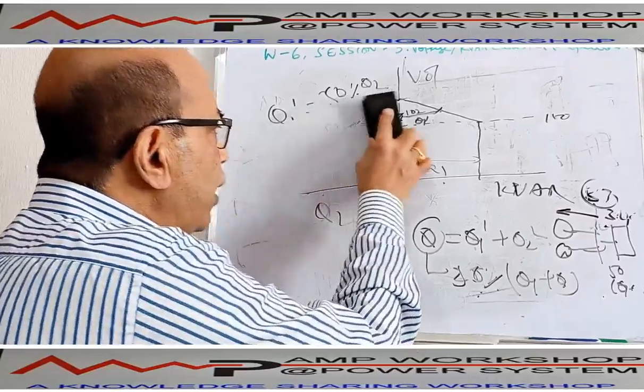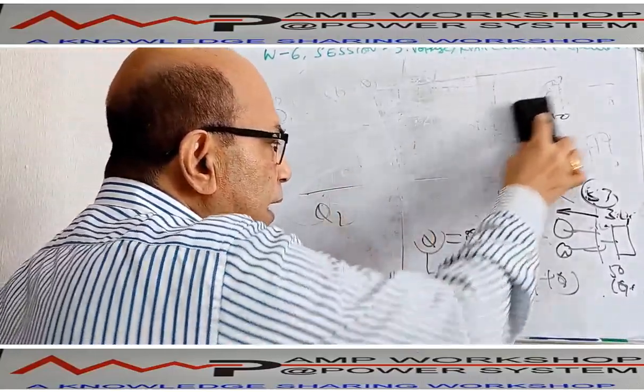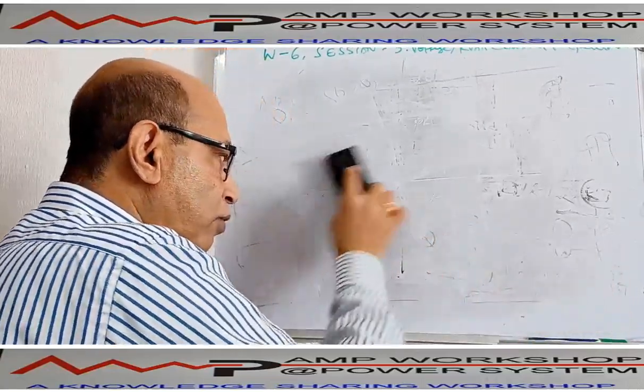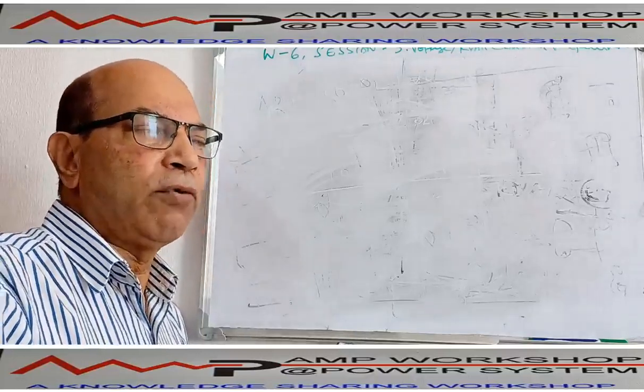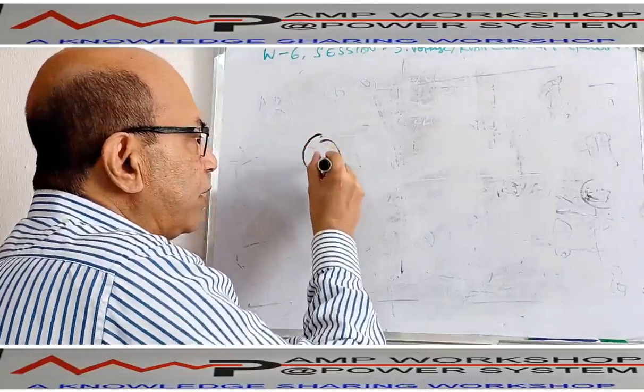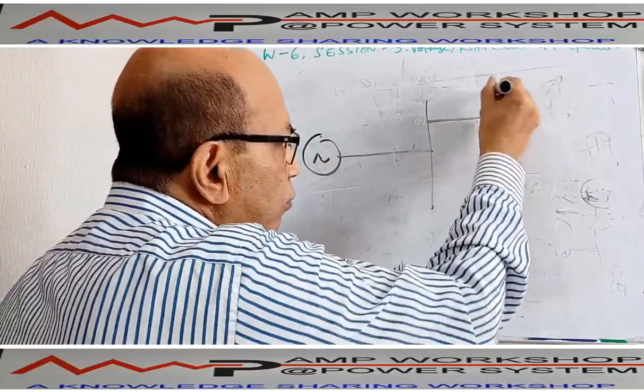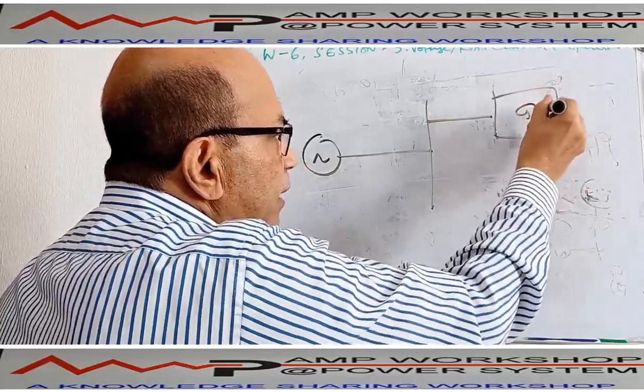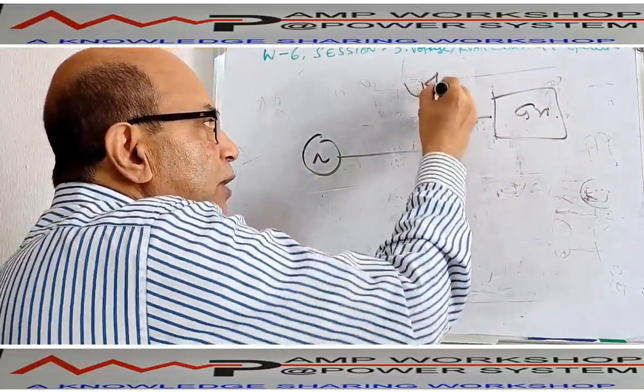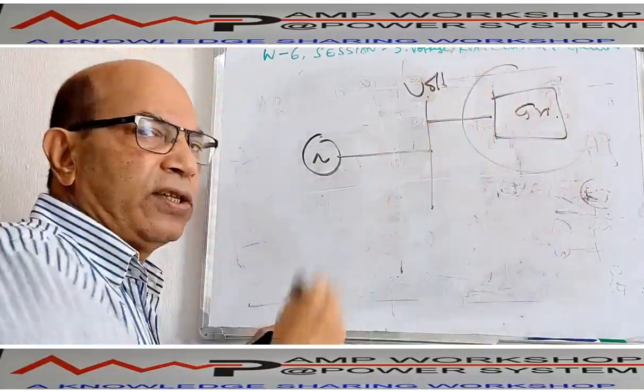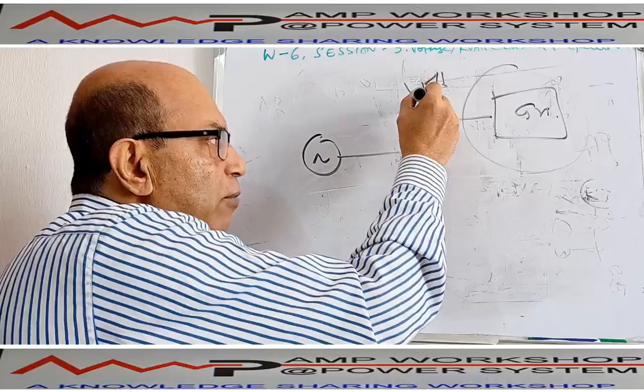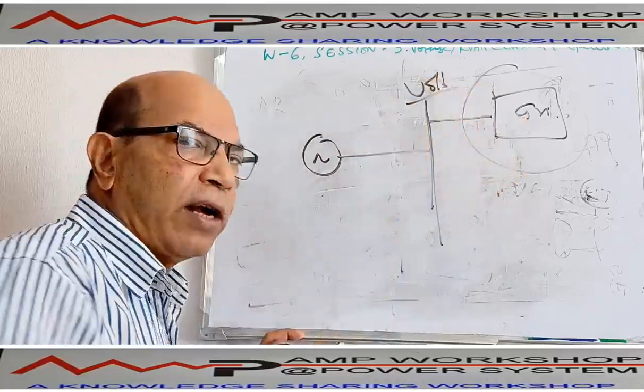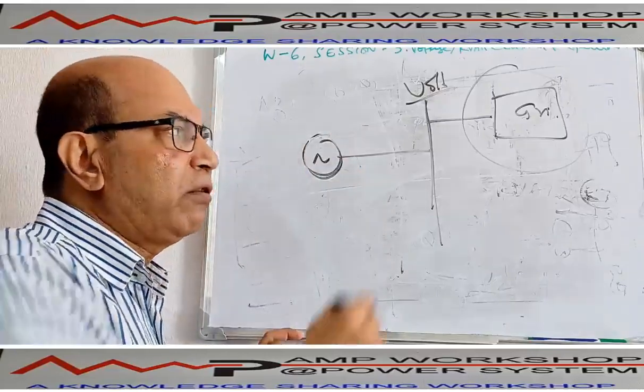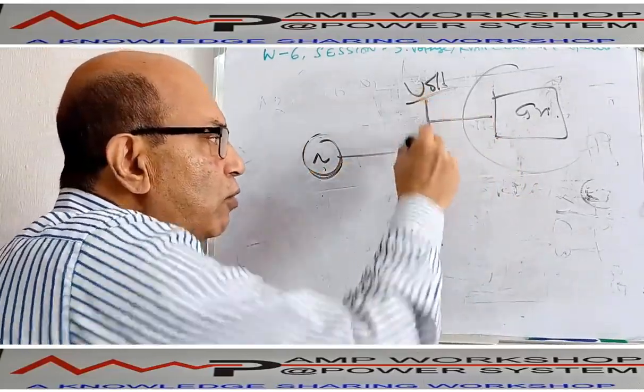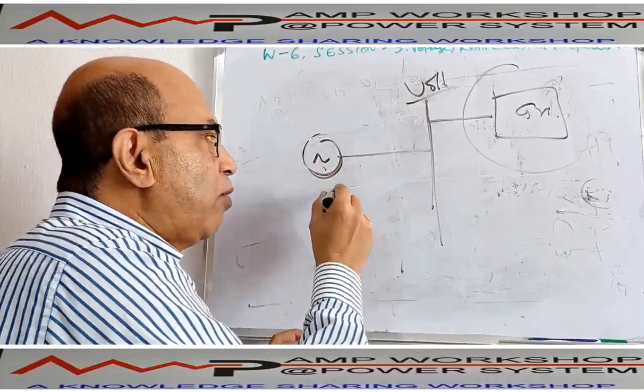Droop voltage mode we use when multiple machines are operating in parallel with different characteristics and different control devices. Then we use this droop mode of operation. Another use of droop mode: suppose this is a generator running with a bus and that bus is connected to the grid. When the grid is running, it has a constant voltage, that means the bus voltage is maintained constant. We can say this is an isochronous system running with a constant voltage. In that case, as we have already said, in isochronous operation you cannot change the bus voltage. Now this machine is small in comparison to the grid, so this machine cannot control the bus voltage. So this machine must be working in the droop mode.